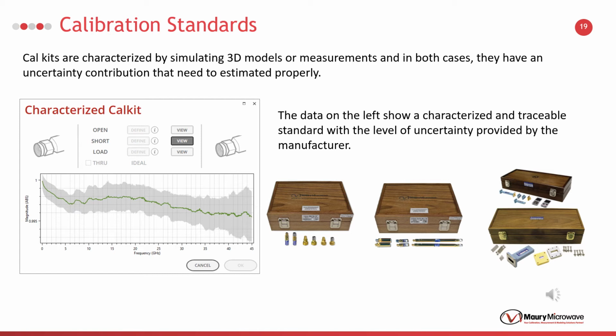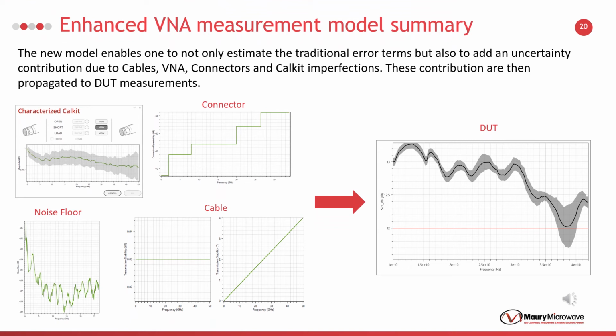Calibration kits are characterized by simulating 3D models or measurements. But in both cases, there are uncertainties due to manufacturing tolerances and environmental effects. A calibration kit's uncertainty parameters must be estimated and provided by the manufacturer. Characterization of the standards should be traceable to a reference standard. After calculating all uncertainty contributions of the enhanced VNA measurement model's subnetworks, S-parameter uncertainty can be measured. Uncertainty contribution of each component can also be analyzed individually or altogether.